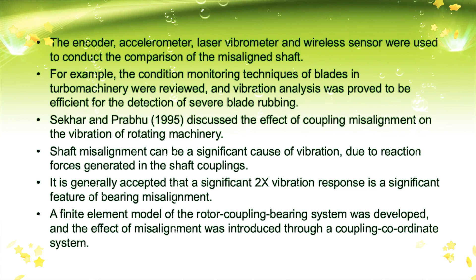In 1995, Sekhar and Prabhu discussed the effect of coupling misalignment on the vibration of rotating machinery. Shaft misalignment can be a significant cause of vibration due to reaction forces generated in the shaft coupling. It is generally accepted that a significant 2x vibration response is a significant feature of bearing misalignment. From that, a finite element model of the rotor-coupling-bearing system was developed, and the effect of misalignment was introduced through a coupling coordinate system.